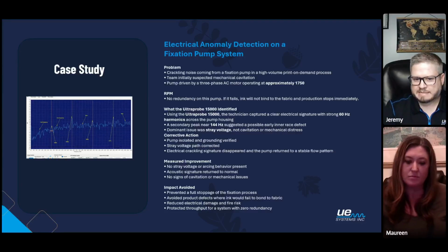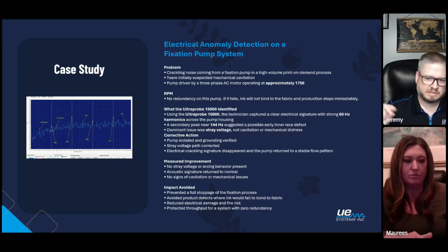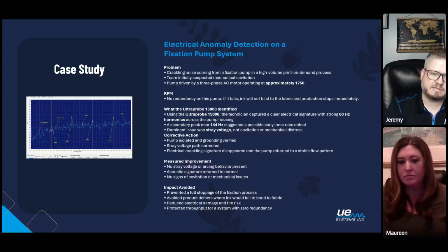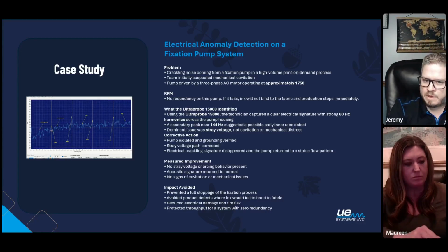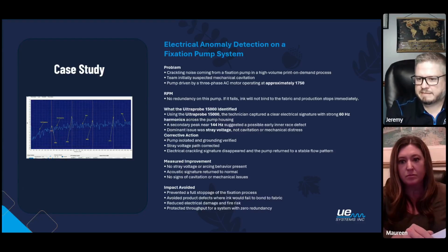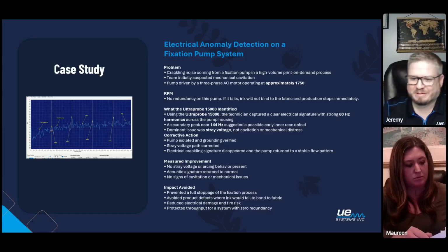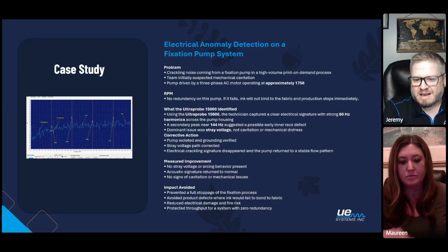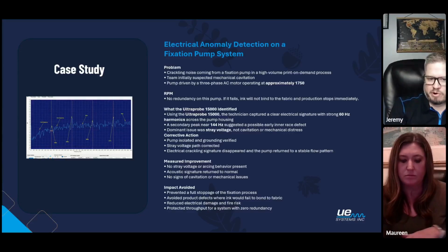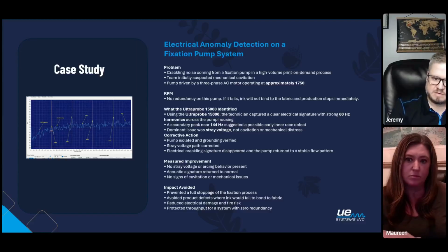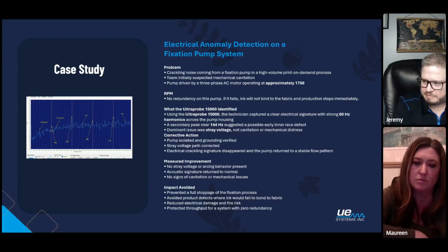And viewing those harmonics, they could see some of the voltage in there that was showing the stray 60 hertz electrical anomalies. And then there's also some peaks. It's kind of hard to see in the picture there. You probably can't view it there. But around 144 hertz, there were some peaks there as well. So that kind of suggested there might be some early bearing wear. But the real issue wasn't the mechanical issue. It was that 60 hertz harmonics that was appearing there.